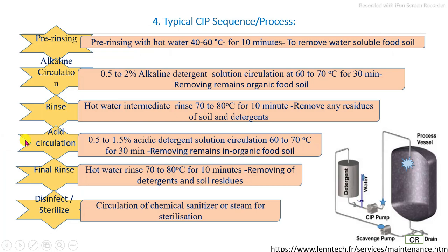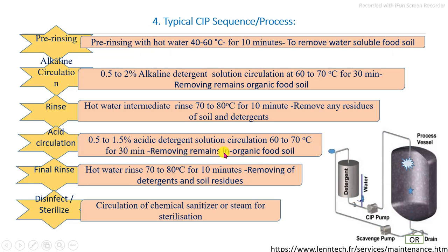The fourth step is the acid circulation or acid cleaning process using 0.5 to 1.5 percent acid — such as nitric acid solution or hydrochloric acid solution — at 60 to 70 degrees Celsius, circulated continuously for 30 minutes to remove inorganic food soils present in the processing line. Then a final rinsing with hot water at 70 to 80 degrees Celsius for 10 minutes completely removes remaining soils and detergents.